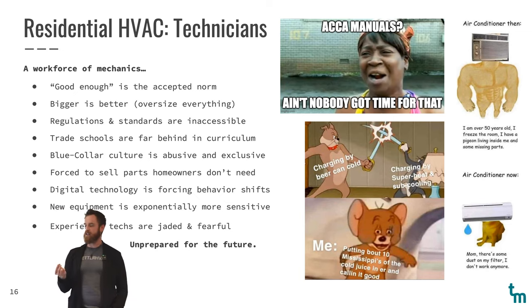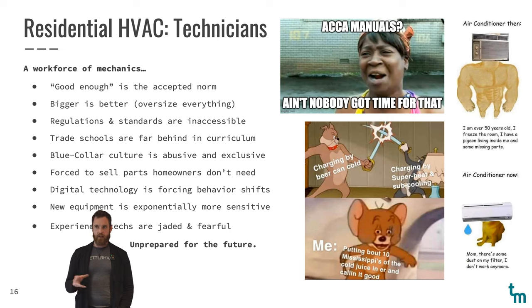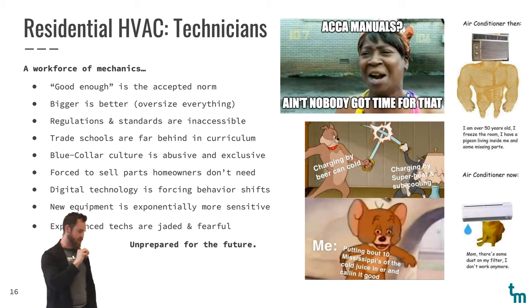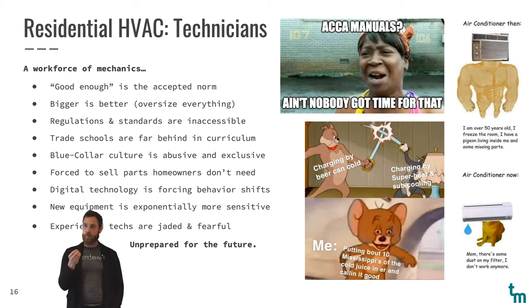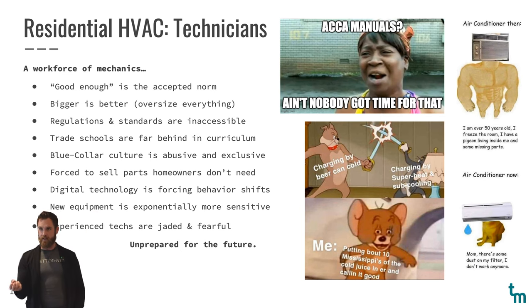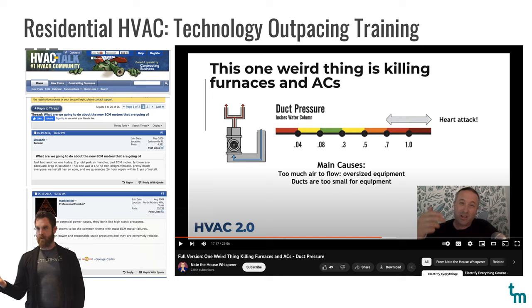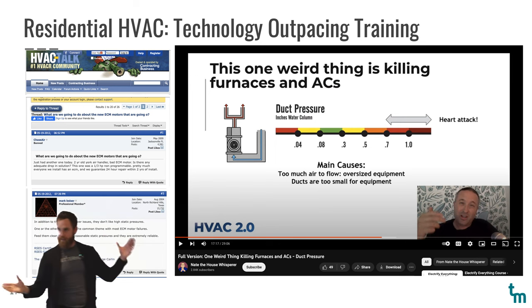There's no incentive for techs to go outside the scope of the equipment swap. A lot of them don't even think about the ductwork, let alone the envelope of the entire home. These shifts, these challenges for techs, and the speed at which technology is changing, the new equipment is so much more sensitive than previous equipment. PSC motors used to be the norm, and a lot of homes have switched over to ECM motors. These ECM motors are failing within the first couple of years, causing an insane spike in warranties, because the techs just do a swap, thinking it's the same tonnage, pop it in, and it mostly works the same. No commissioning at all, commissioning's not even a thing.